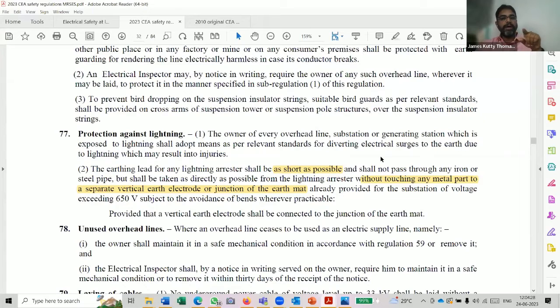But please go through the other portions of this clause. It is the same as the 2010 regulation. As you know, in India, we implemented the international lightning protection standard IEC 62305/2010 from 2015 onwards, which is after the year of the old standard. Still, we are keeping the same wordings with this regulation. Actually, it is making it more confusing, whether the lightning protection earthing and the power system earthing can be interlinked. Yes, all of our standards such as NEC 2023, IS 732, IS 3043 and IEEE standards support this, to avoid the potential difference between the two portions and thereby avoid damages due to step potential.